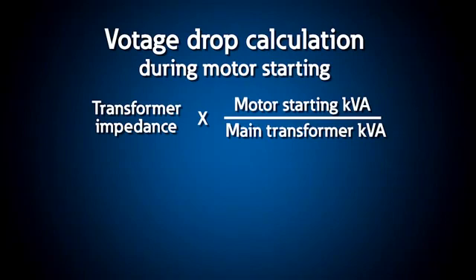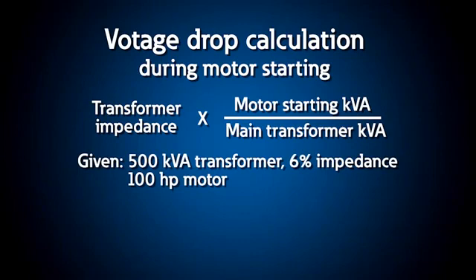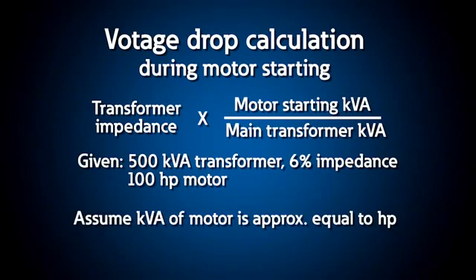For example, if the main transformer facility is rated 500 kVA with 6% impedance and you are starting a 100 horsepower motor across the line, you would estimate the voltage drop by the following method. First, assume the kVA of the motor is approximately equal to its horsepower.